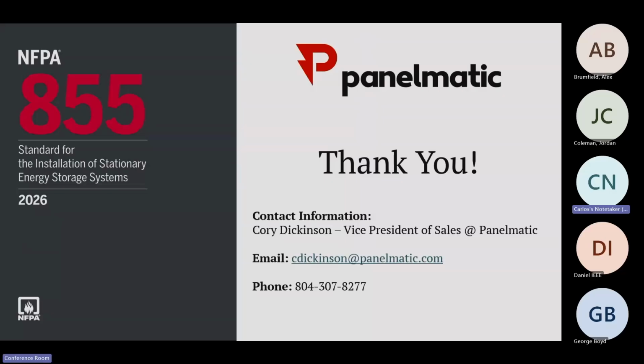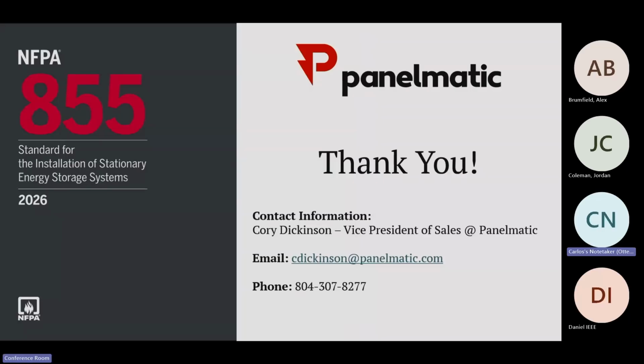The way we've designed these systems so far, at least at our company, is at 2.5% if it picks it up, it starts moving air in that room. If it gets to 5%, it continuously moves and doesn't stop. If it goes past 5%, it opens the doors and shuts off. This is NFPA 855? Yes, sir.